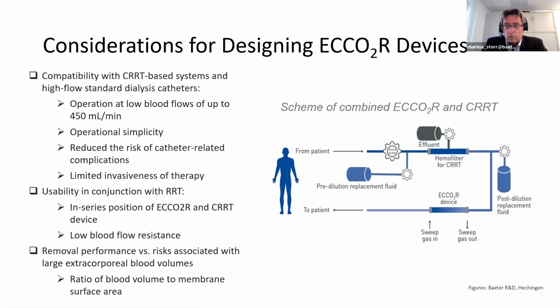Therefore, we had to consider requirements with respect to blood flow resistance, but also regarding the in-series position of the ECCO2 device relative to the CRRT device. And here on the scheme on the right, you see a setting where the ECCO2 removal device is positioned in distal position relative to the CRRT filter. But of course, the proximal position would also be conceivable.